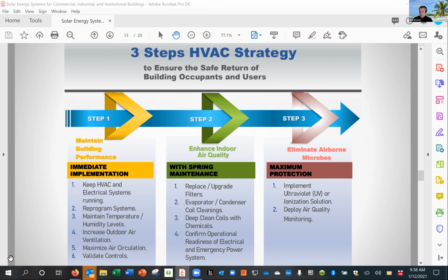One of them is UV lights, and the other is something called needlepoint bipolar ionization — I know that's a mouthful, so we'll just call it bipolar for now. UV lights are basically fluorescent, high-powered ultraviolet lights that shine like sun rays coming through a window on a surface area, and all the air that goes through that — whatever particulate, foreign matter, bacteria, organisms living or not — that passes through that lit area is killed on contact.